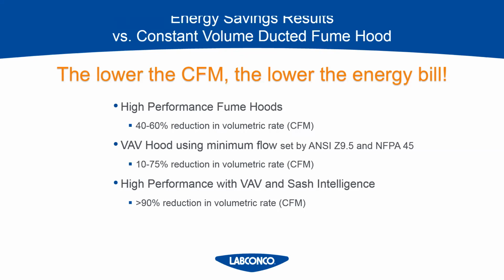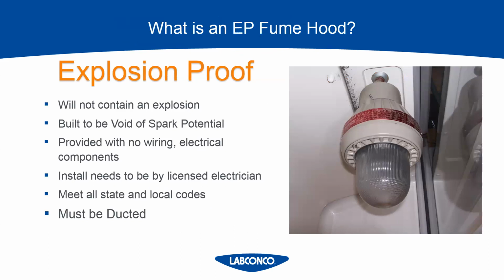But once again, the real fact that we're looking at here is the lower the CFM, the lower the energy bill. So if you are going ducted, look at that CFM number. That's what you can compare from hood to hood, manufacturer to manufacturer, and make sure that you're getting the least amount of CFM. So explosion proof, once again, this is a topic that could probably be its own webinar, but the bottom line is if you need an EP hood, it must be ducted. So that's kind of just the rule that we're going to go with on this webinar. If you have any other questions on that, please email me. Like I said, it's a whole topic in itself.